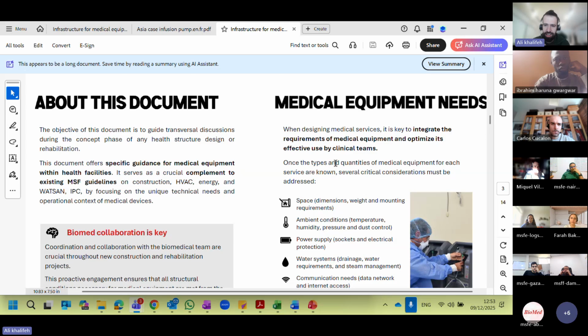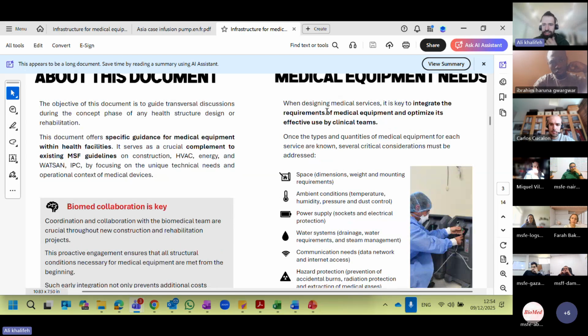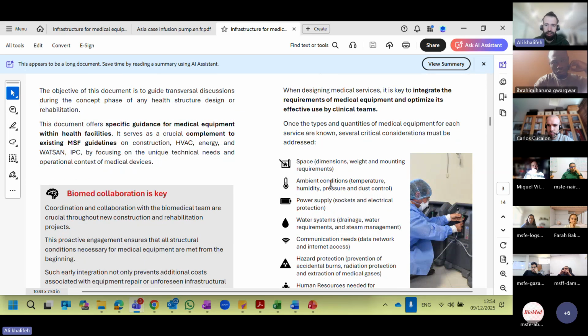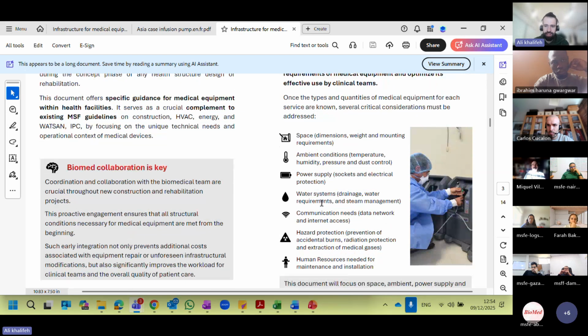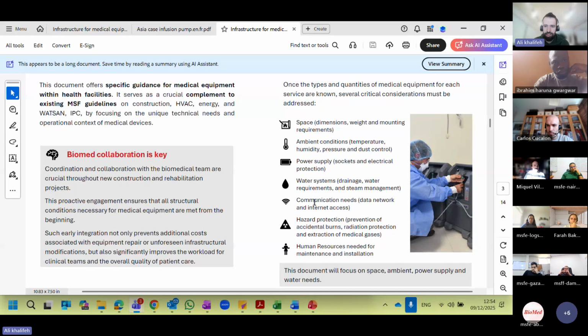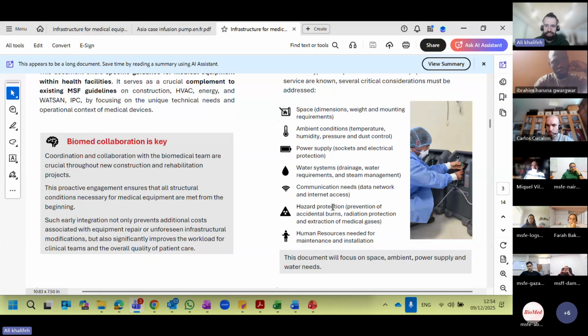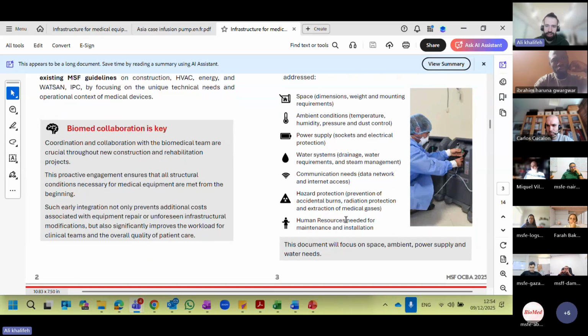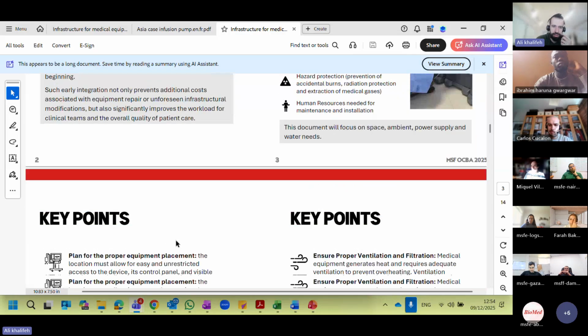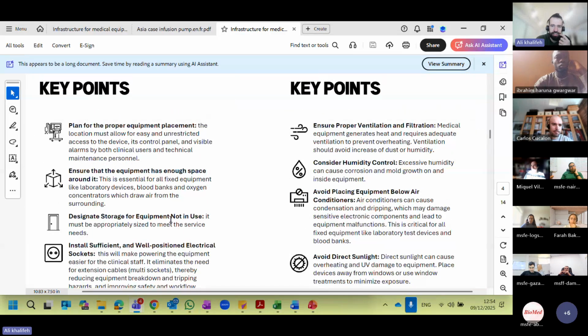So for medical equipment needs, whenever we request new equipment, or a clinical team needs to implement it in their department, we need to check the space, the ambient conditions, the power supply, the water system, communication needs, hazard protection, and the human resources needed for maintenance and installation. This is what we need to check for each piece of equipment. Where we can check this, we have here the key points.